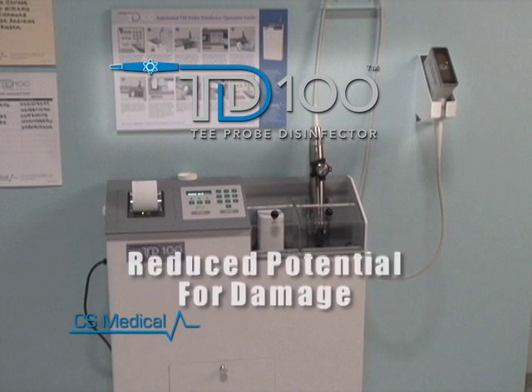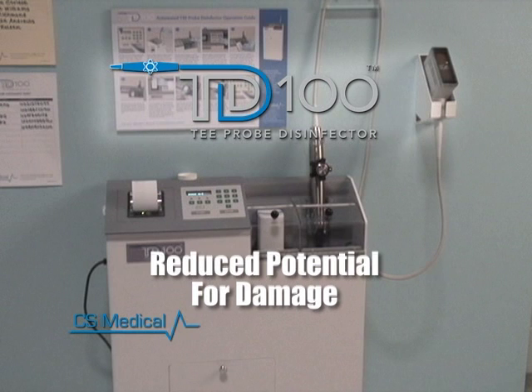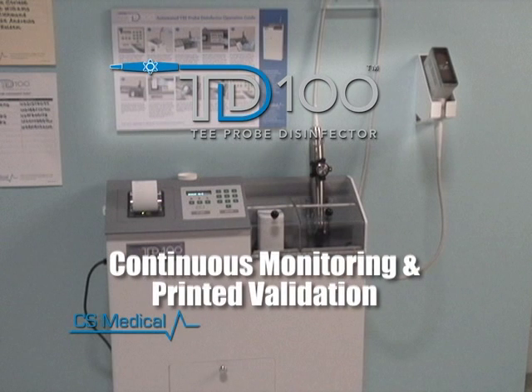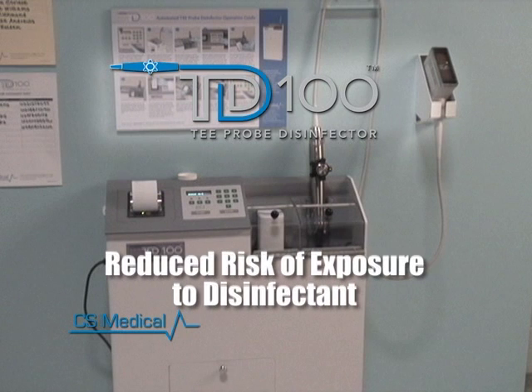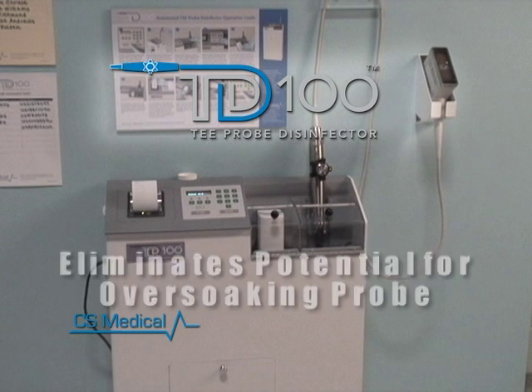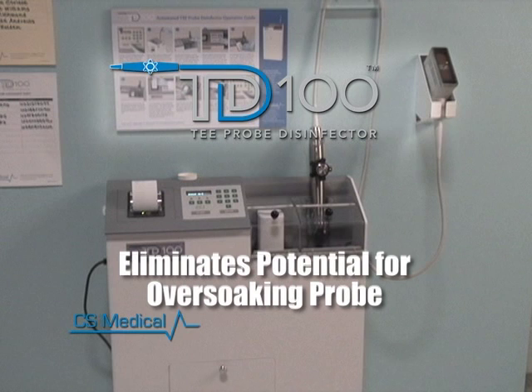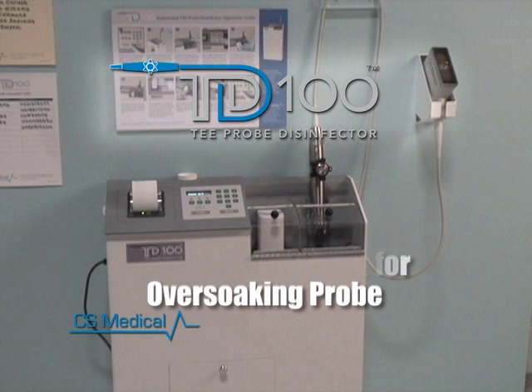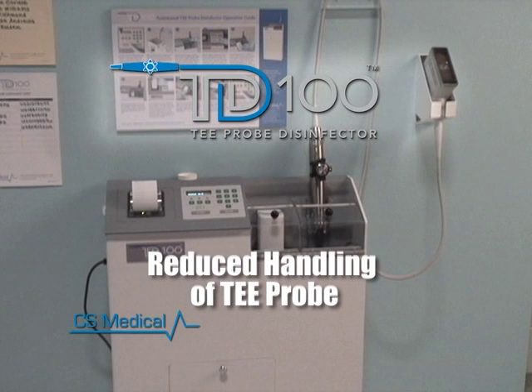Allows you to reprocess your probes near the area of use, dramatically reducing the potential for damage. Provides continuous monitoring of all functions and generates a printed validation at the end of the completed disinfection cycle. Reduces the risk of exposure to harmful high-level disinfectant. Eliminates the potential for over-soaking the TEE probe, since at cycle end, the reservoir is completely empty. Reduces handling that may cause probe damage, resulting in costly repairs to your TEE probe.